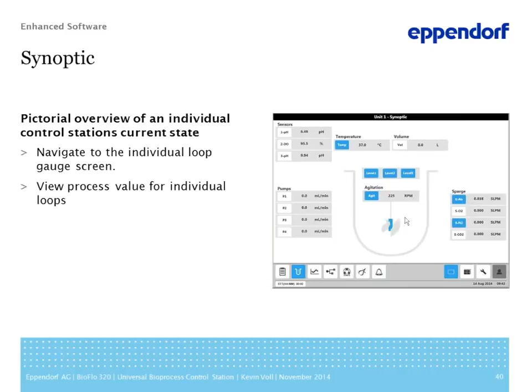So for agitation, temperature, sensors, this is where you would set the set points and also really define how the system is going to be controlled. With pH, obviously you'd have deadband values that you would be able to set. Proportional and integral values are available for the sensors so that you can control the rate of change and the overall programming for the control of the unit.